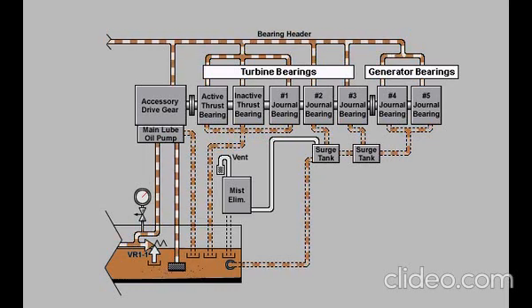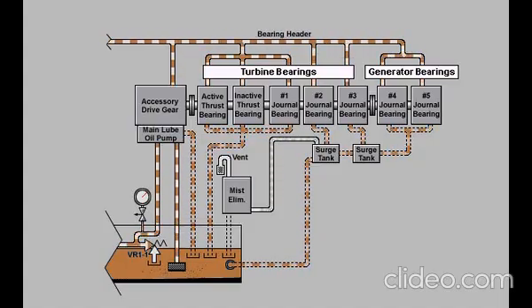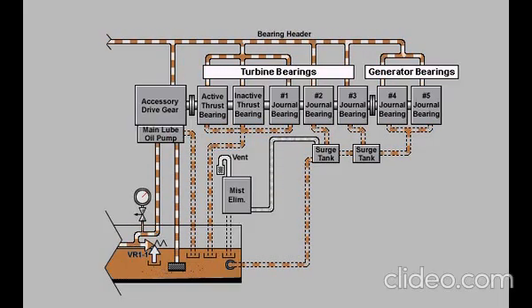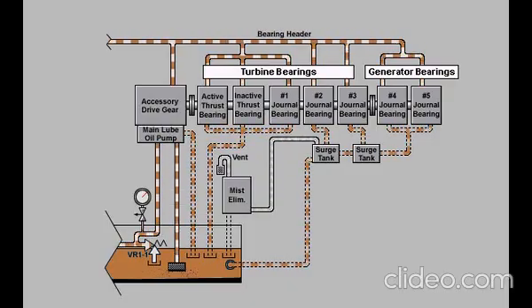The exhaust fan on the mist eliminator draws air from the surge tanks in the turbine base. Oil droplets suspended in the air stream are separated by coalescing filters within the mist eliminator. The mist-free air is vented to atmosphere and any recovered lube oil drains back into the lube oil tank.